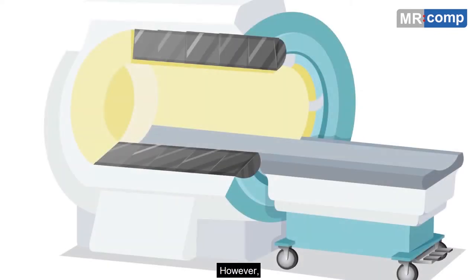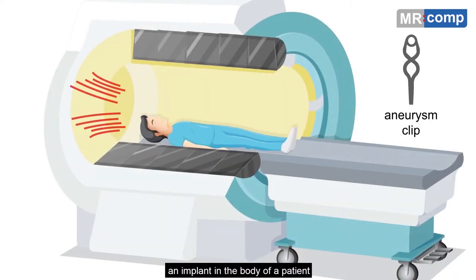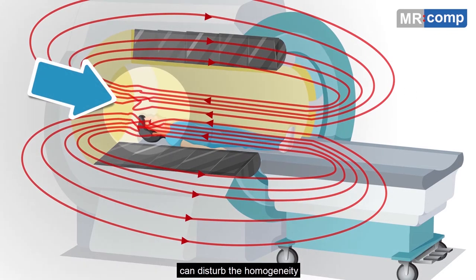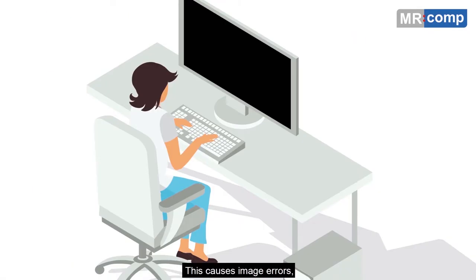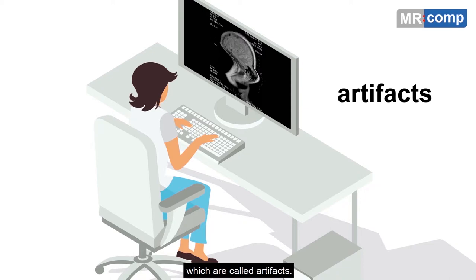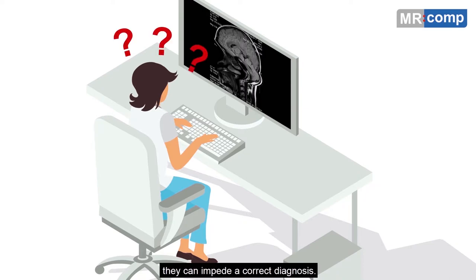However, an implant in the body of a patient can disturb the homogeneity of the static magnetic field. This causes image errors, which are called artefacts. If they occur, they can impede a correct diagnosis.